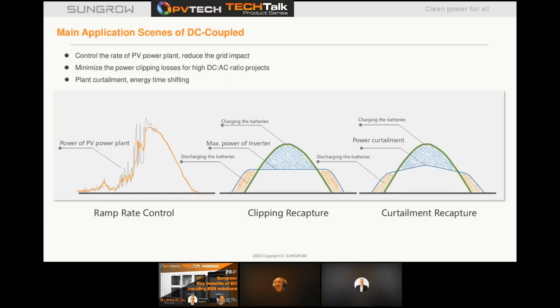So, typical applications - here we have some of the main areas we see DC coupled solutions working. On the left graphic, we see unpredictable power due to fluctuations of irradiance. For this, we can offer ramp rate control, a way of smoothing the power swing or reducing the impact of power changes with a combination of PV yield and stored energy from the batteries.